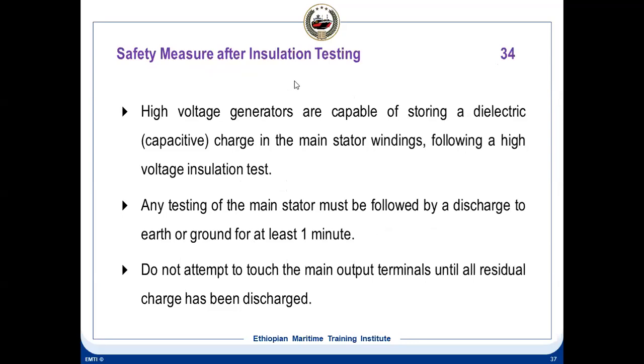The safety measures after insulation testing are very important. Whenever you measure any insulation, whether it is a motor or generator or anywhere, you must discharge any static charge acquired during the insulation testing. You must have seen, when you do a Megger test of a motor and then remove the Megger, there are still some residual charges. You need to take a wire and ground it so that any residual charges are discharged. High voltage generators are capable of storing a dielectric charge in the main stator winding following a high insulation test. So any testing of the main stator must be followed by a discharge to earth or ground for at least 1 minute.